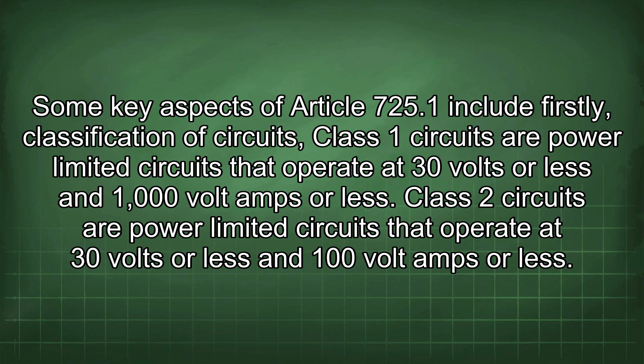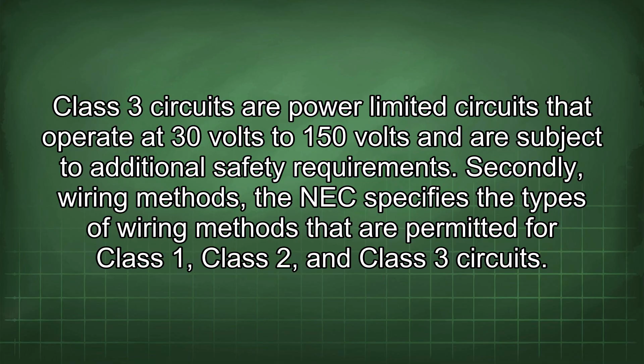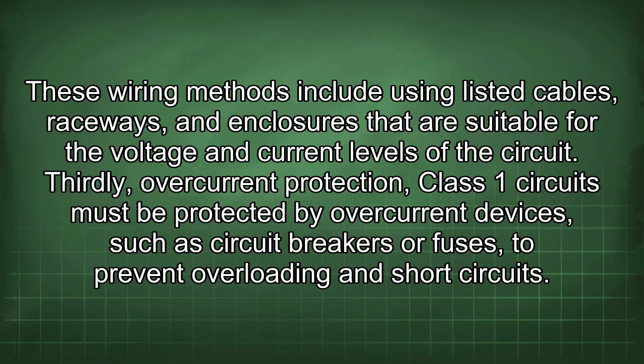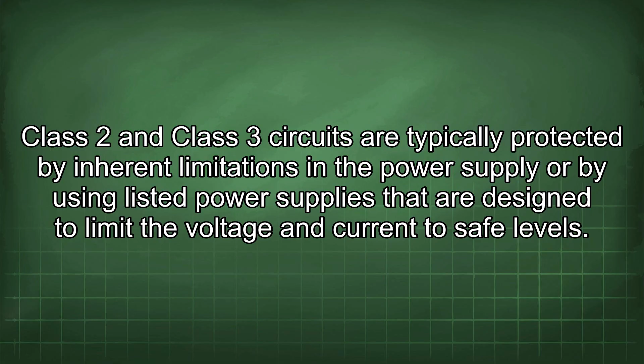Secondly, wiring methods. The NEC specifies the types of wiring methods that are permitted for Class 1, Class 2, and Class 3 circuits. These wiring methods include using listed cables, raceways, and enclosures that are suitable for the voltage and current levels of the circuit. Thirdly, overcurrent protection. Class 1 circuits must be protected by overcurrent devices, such as circuit breakers or fuses, to prevent overloading and short circuits. Class 2 and Class 3 circuits are typically protected by inherent limitations in the power supply or by using listed power supplies that are designed to limit the voltage and current to safe levels.